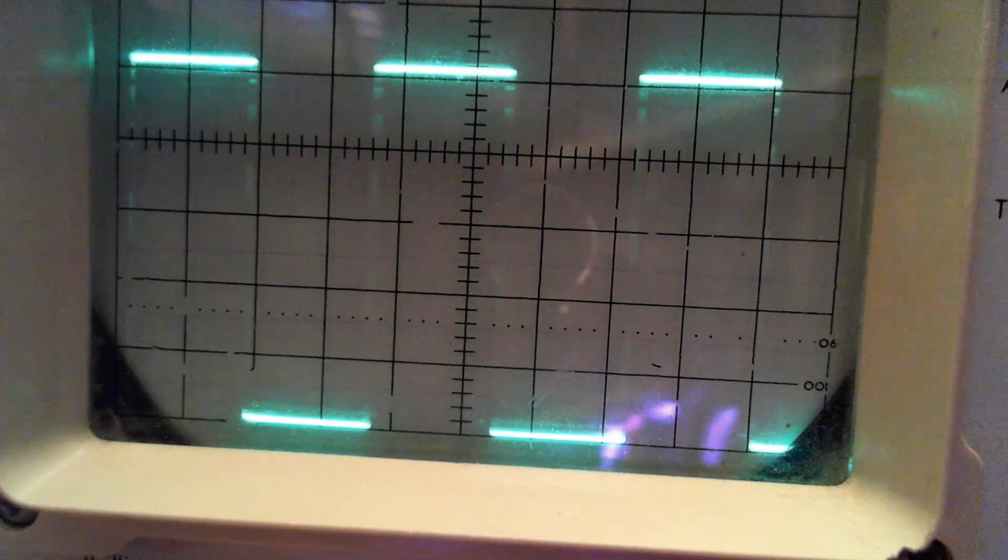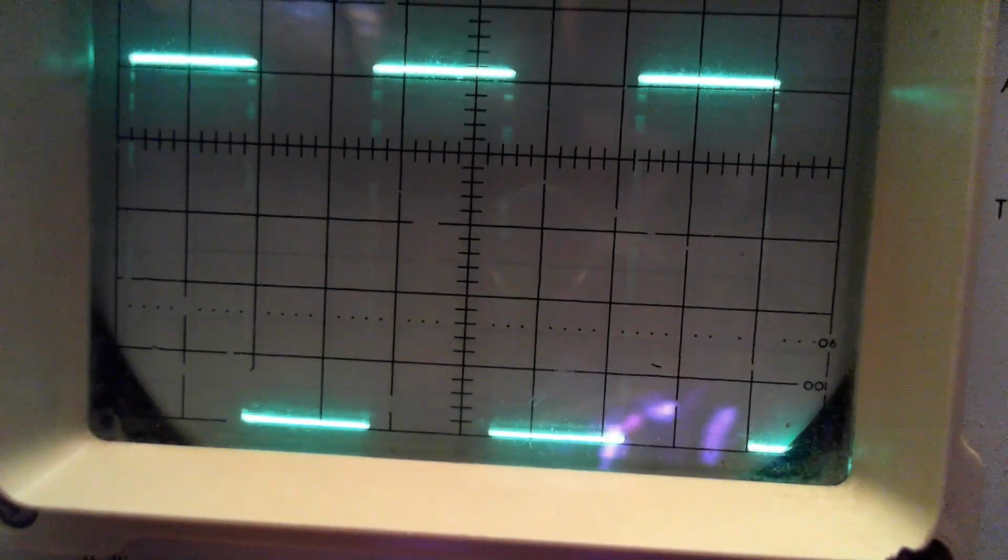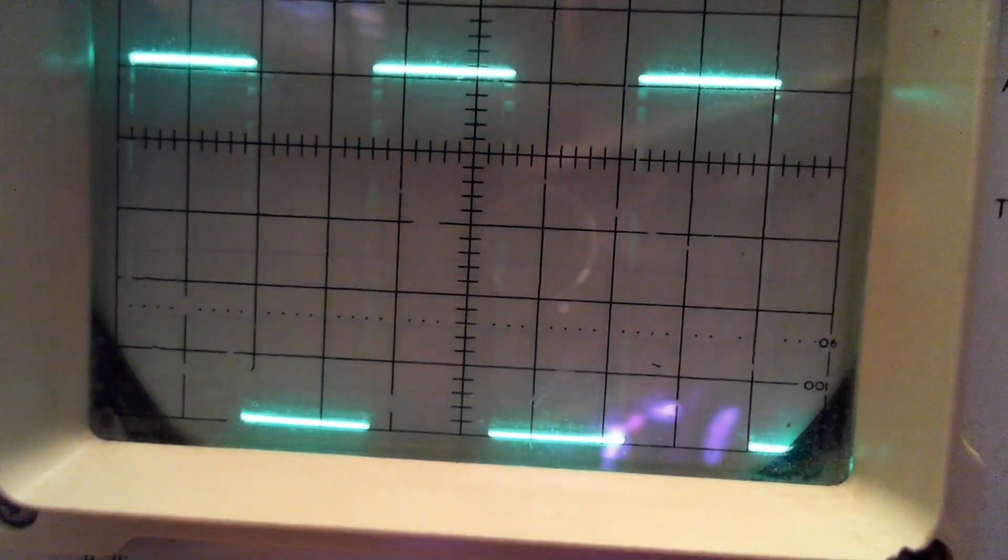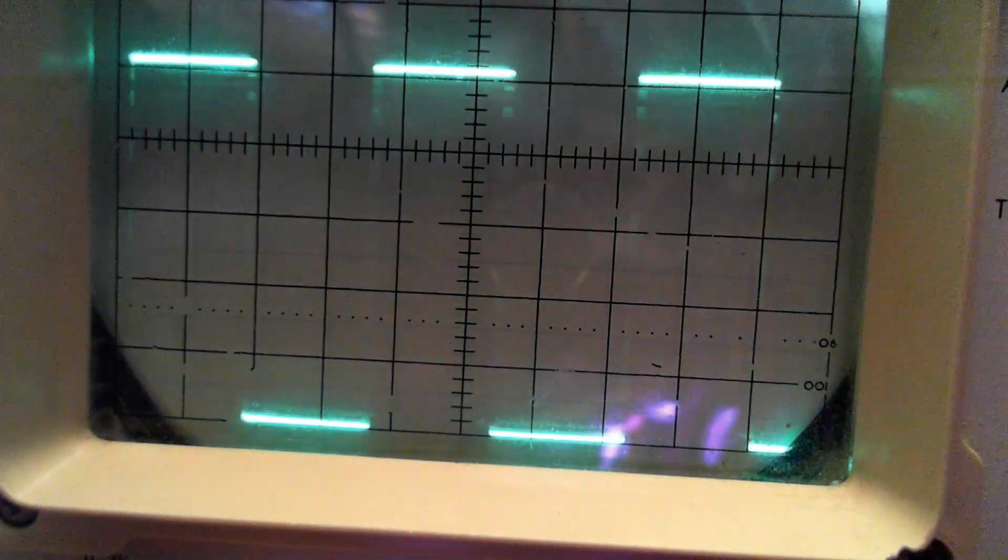Okay, now the adjustment is R304 set calibration. R304 is easily accessible. I already checked that. Now, 304 would be this one. Let me just read it right on the board.